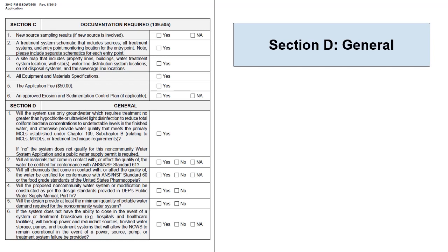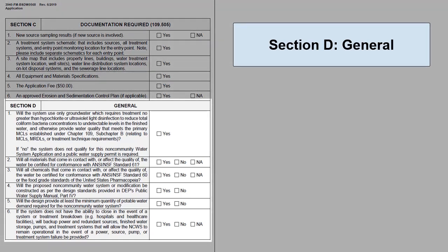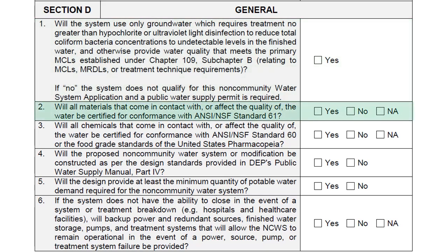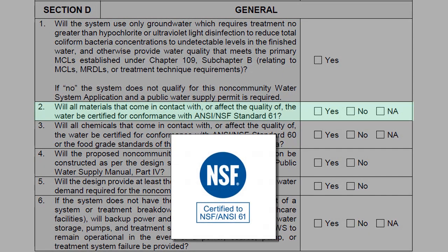Section D is intended to ensure that the system is following the general guidelines necessary for the approval of their non-community water system application. The applicant must first verify that they are using only groundwater, which requires treatment no greater than hypochlorite or ultraviolet light disinfection to meet all primary MCLs established under Chapter 109. Otherwise, the system does not qualify to use the non-community water system application and would instead be required to submit a public water supply permit. All materials must be acceptable by the department. If materials are certified for conformance with ANSI NSF Standard 61, they meet this requirement. If not, the department will review the specifications provided to see if the materials are acceptable.